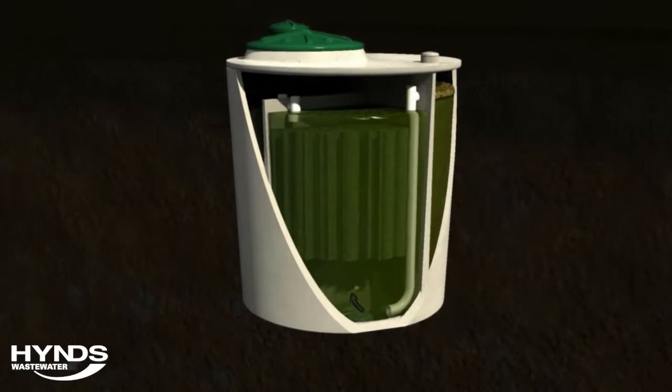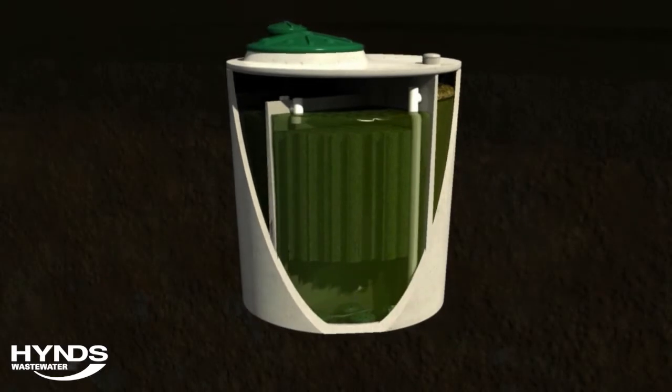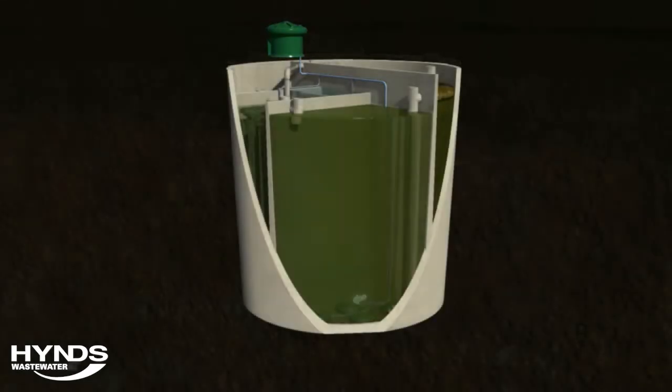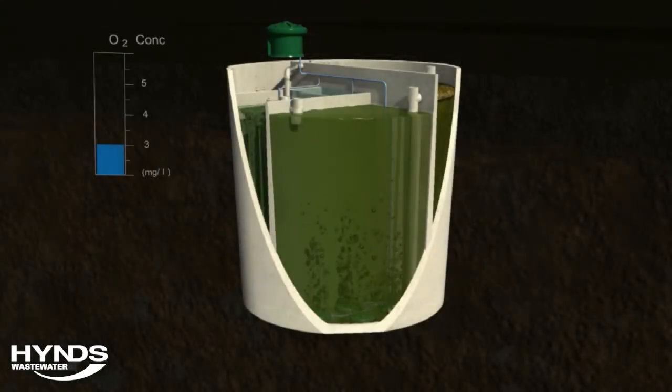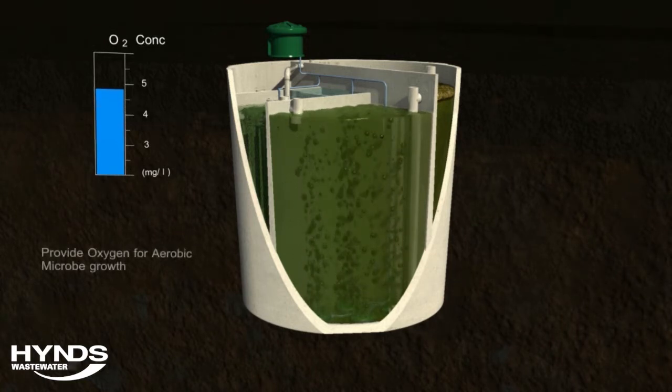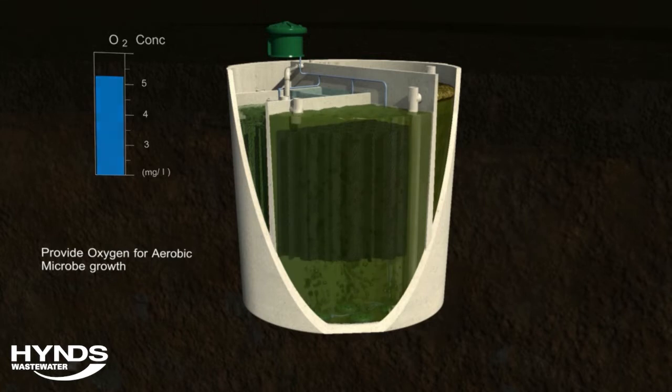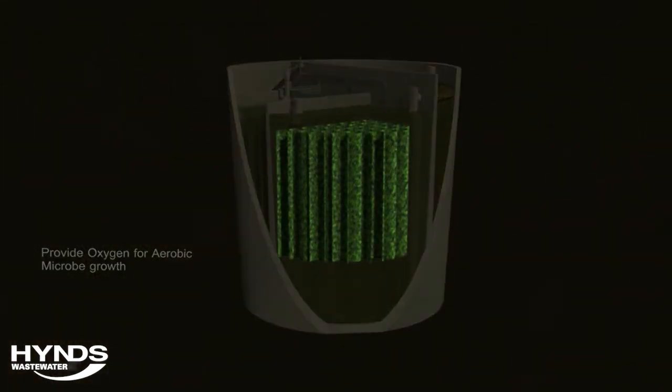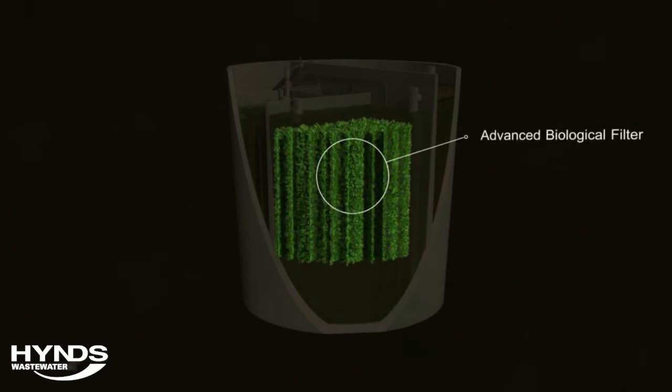The water then enters the secondary stage of the treatment process. A blower located on top of the tank forces air into the wastewater through specialized fine-bubble air diffusers. This oxygen in the air is absorbed by the water, creating an environment that is suitable for aerobic microbe growth. Filter media fills this chamber and the large surface area creates a perfect place for the microbes to grow.